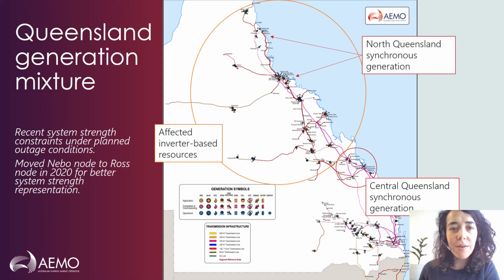Here I am showing on the map the spread of different generation types across the Queensland network to give a sense for the fact that, for example, in central Queensland, there's a centre of synchronous generation, which has certain system strength requirements and properties. In the north, there are some synchronous generators right up at the north, which are contributing to system strength. And then in between, we're seeing increasing penetration of inverter-based resources, and that's something we need to plan for from a system strength point of view. We previously had a system strength node down at Nebo, and we decided to move the node up to Ross earlier in 2020 so that we could be focusing more clearly on where system strength issues are emerging.